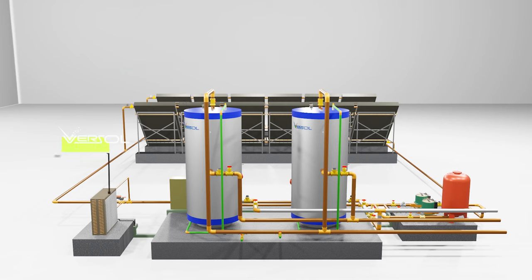The emergency cooler is a safety feature that prevents overheating of the system by releasing excess heat through a heat exchanger to the outside environment, thus protecting the system components and ensuring safe operation. An expansion vessel is a container that allows for the expansion and contraction of the heated water as it moves through the system, helping to maintain stable pressure levels and preventing damage to the system.